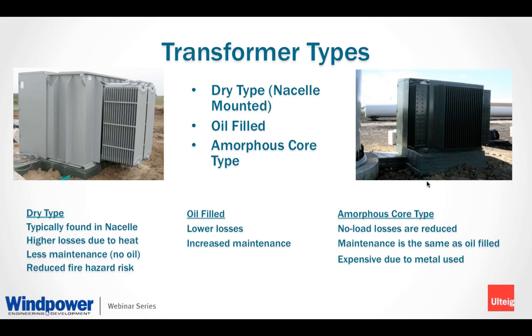Oil-filled transformers, these are the transformers you see with the fins. Both of the ones pictured in the slide right now are the oil-filled type. These units tend to be cheaper. They're less expensive, and they have shorter lead times. Sometimes the no-load losses can be specified to be in certain amounts based on your manufacturer. And this can result in a very cost-effective option while still keeping the no-load losses in check.